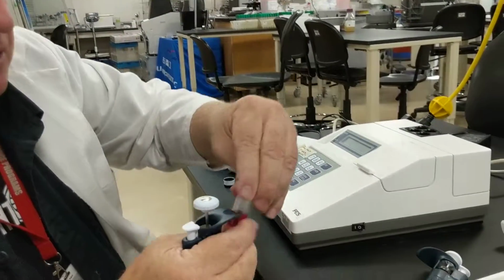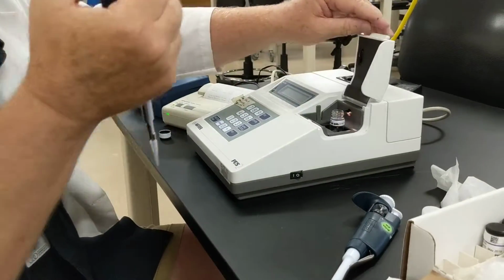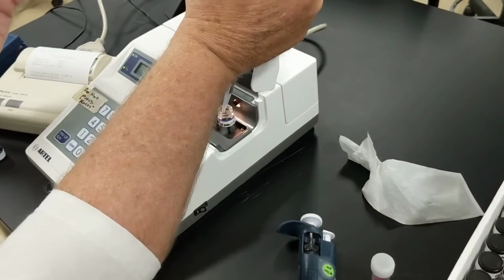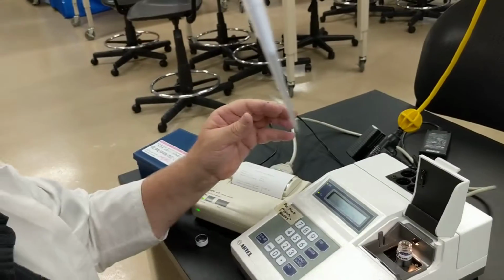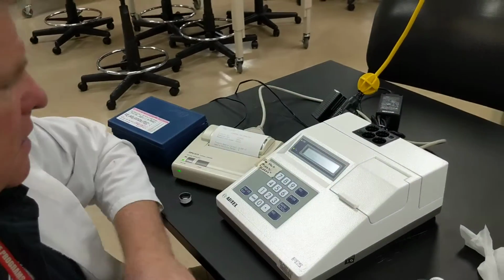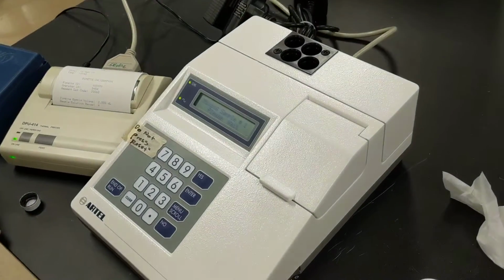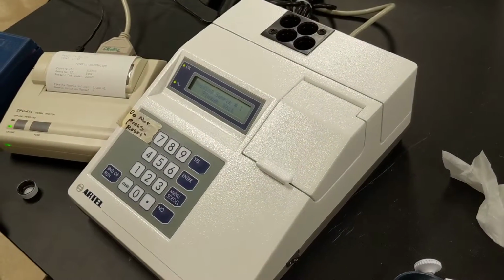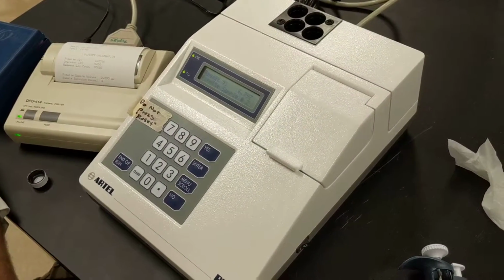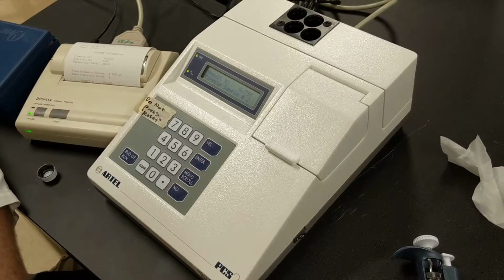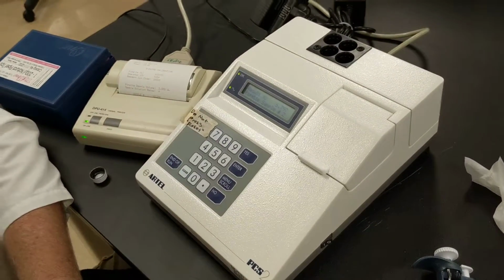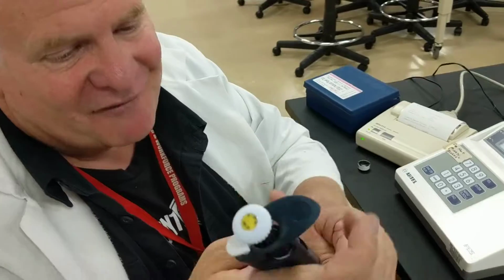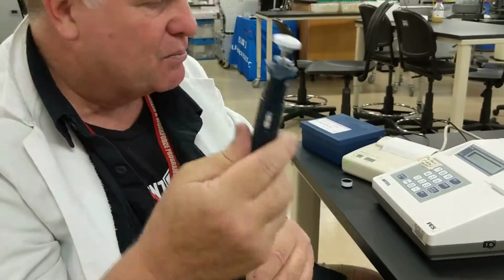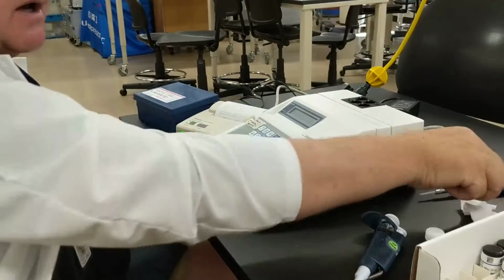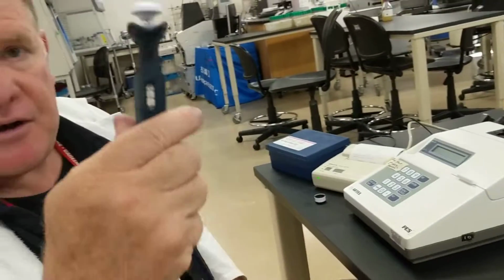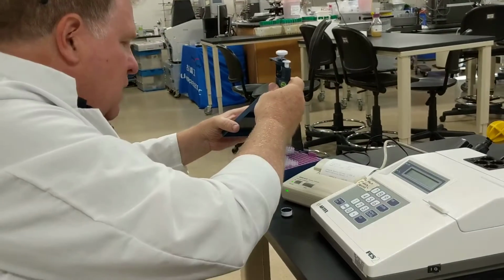I would then go into my bottle, and then I just put it off on the side, and I make sure that it's all gone. And I shut the top and hit enter, and what it's going to do is measure it, and this one says that it resulted in 6.797. So this pipette is way off, and if I look at this, it failed calibration a while ago. So what I'm going to do is get hopefully another one that will actually pass calibration.